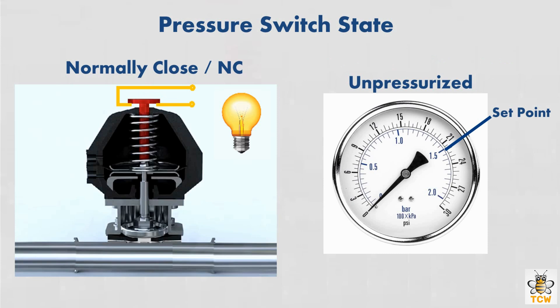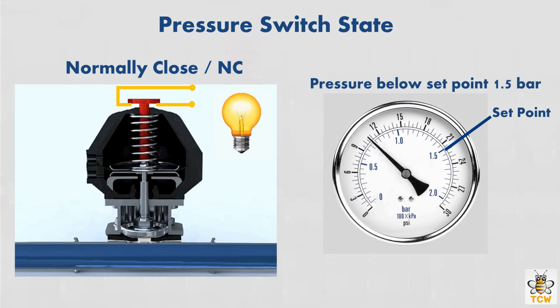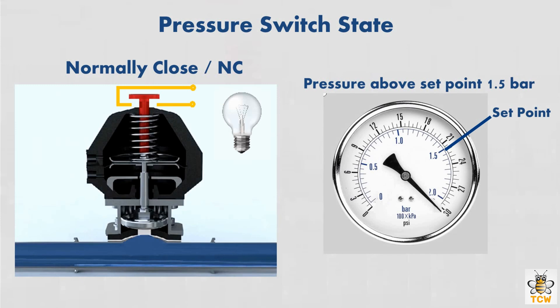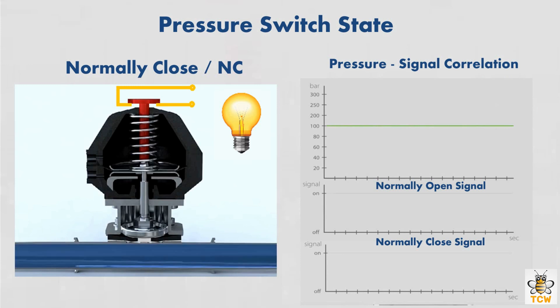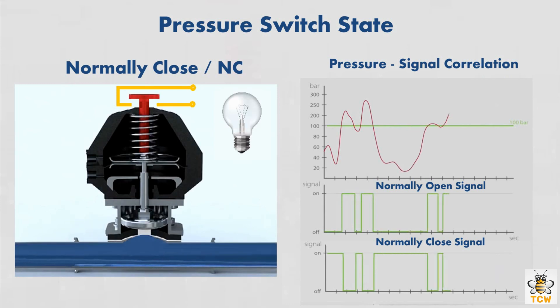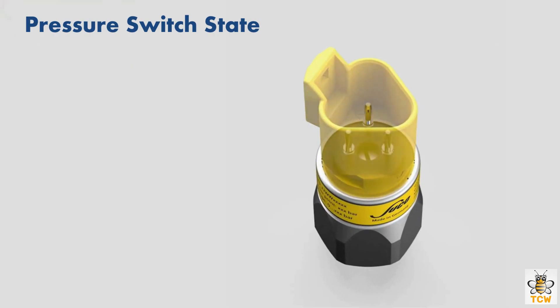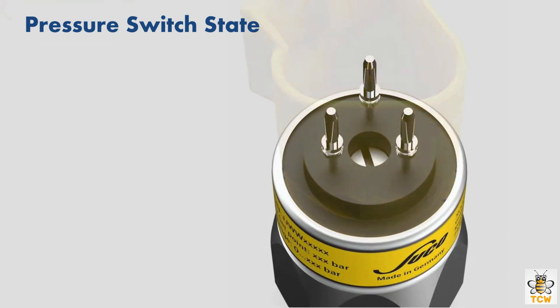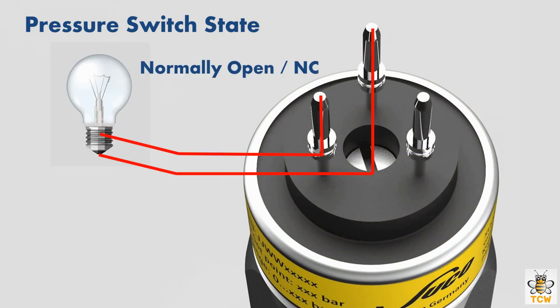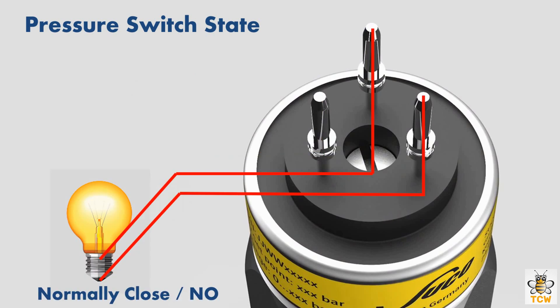The second state is normally closed, or NC. Normally closed is the state where the pressure switch is connected when unpressurized. It remains connected if given a pressure lower than the set point pressure, and will disconnect only when the pressure reaches or exceeds the set point. The normally closed and normally open signal outputs are opposite to each other. Setting the state of the pressure switch is done by connecting certain terminals. Generally, pressure switches have three terminals that can form two pairs of wires — one pair for the normally open signal output, and the other pair for the normally closed signal output.